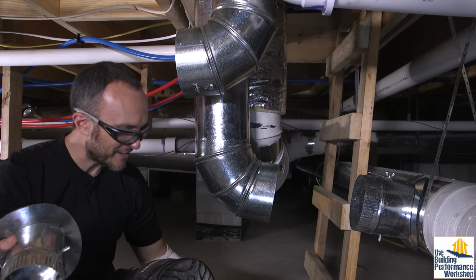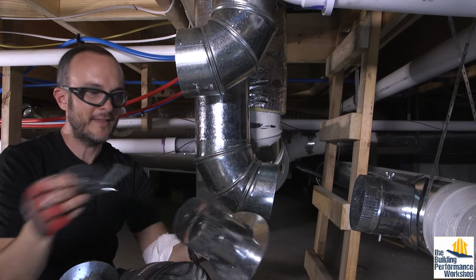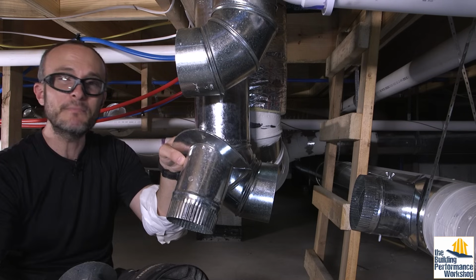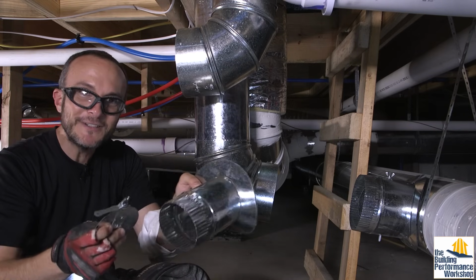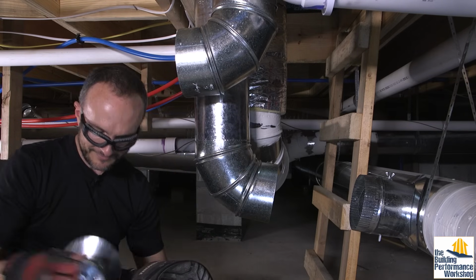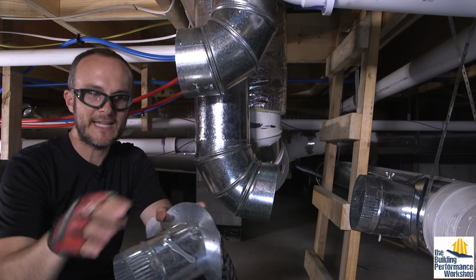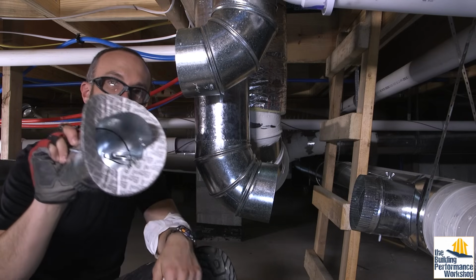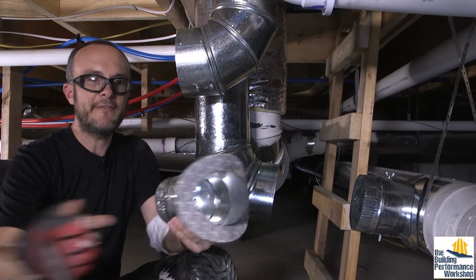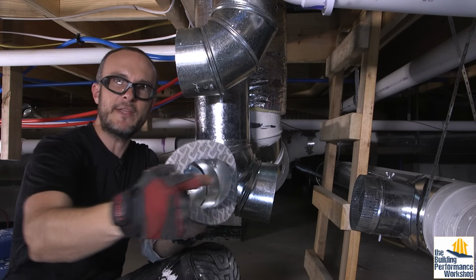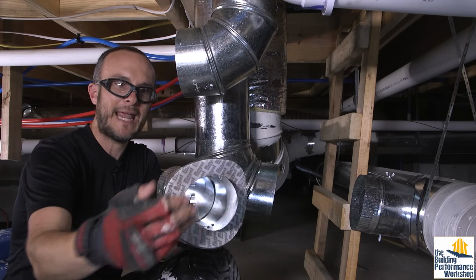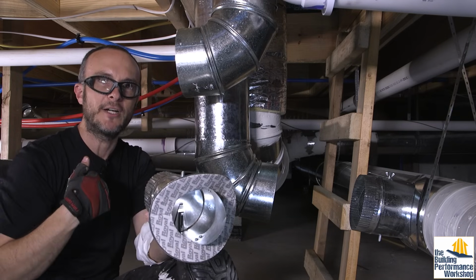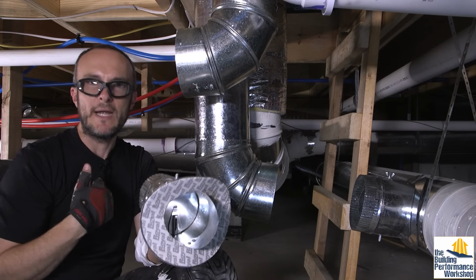To do this, I actually just bought the damper separately with the collar, the takeoff, and they make little holes for you to put a damper into. So that makes it very, very simple. This one, though, has another feature, aside from the fact that they saved you the time of putting the damper in place, and that's called a scoop. So the scoop is made so that if I've got a duct where I've got air moving down this way, I put it in this direction and it will actually catch the air and encourage it to make this 90-degree turn and come this way instead.